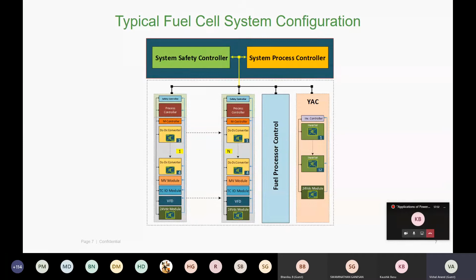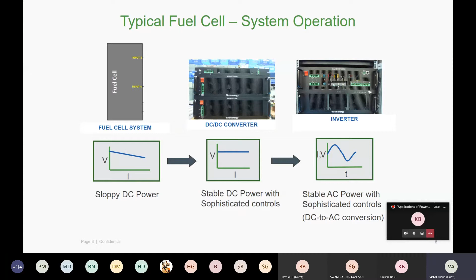Looking at system operation, on the left we have the fuel cell generating DC, and it's a very sloppy DC. Once you start loading the fuel cell, you draw more and more current, and the voltage droops and becomes unstable. This kind of unstable DC is not what loads like, so we introduce a DC-DC converter that converts this sloppy DC into a stable, stiff DC. This stiff DC is then provided to the inverter, which converts stable DC into variable frequency, variable voltage AC with sophisticated control. This is how the entire system looks from the inside.